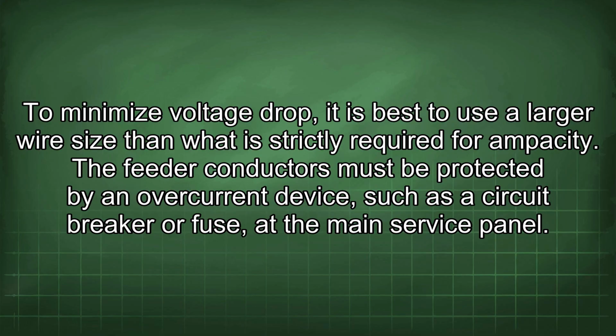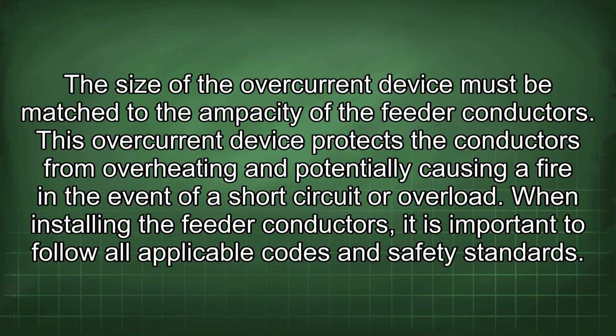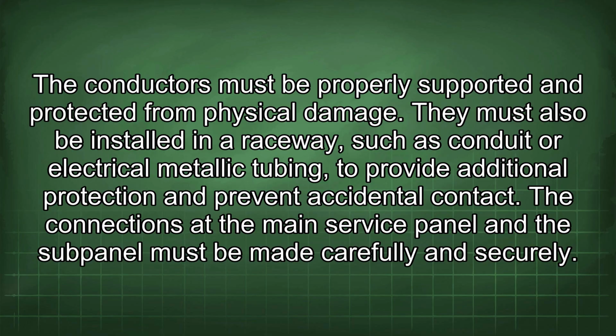The feeder conductors must be protected by an overcurrent device, such as a circuit breaker or fuse, at the main service panel. The size of the overcurrent device must be matched to the ampacity of the feeder conductors. This overcurrent device protects the conductors from overheating and potentially causing a fire in the event of a short circuit or overload. When installing the feeder conductors, it is important to follow all applicable codes and safety standards. The conductors must be properly supported and protected from physical damage. They must also be installed in a raceway, such as conduit or electrical metallic tubing, to provide additional protection and prevent accidental contact. The connections at the main service panel and the subpanel must be made carefully and securely.